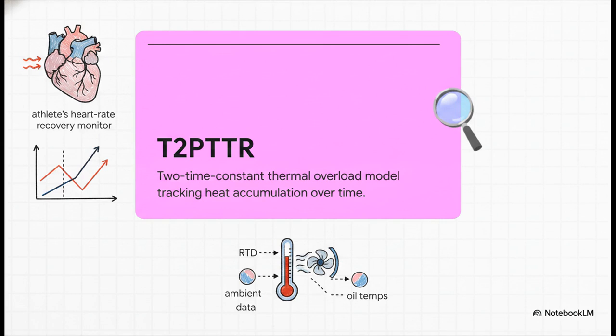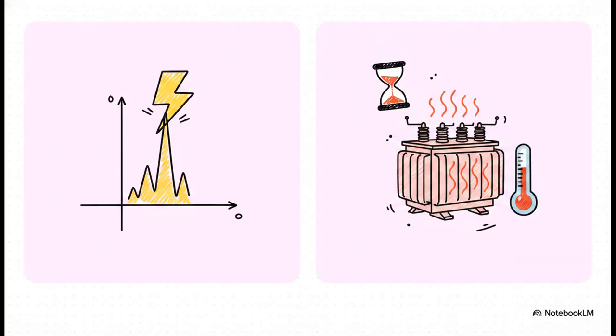It can even take in real-time temperature data from physical RTD sensors, measuring ambient and oil temps, to dynamically adjust its protection curve based on actual cooling conditions. The crucial point here is understanding the difference between these two approaches: simple overcurrent protection only cares about an instantaneous spike in current, but thermal protection tracks cumulative energy over time. And why does this matter so much?